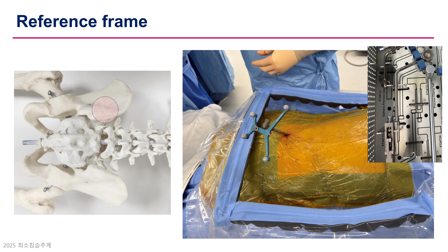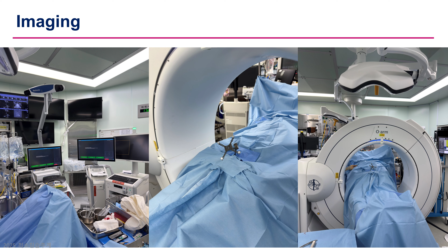I recommend positioning the navigation unit distal to the scope tower. If it is located near the anesthesiology area, the equipment may obstruct the view of the iliac crest reference frame. Once the frame is fixed, we proceed to take the O-arm scan to register the anatomy accurately. After setting the frame, we first check the spinal level and then perform the O-arm scan.